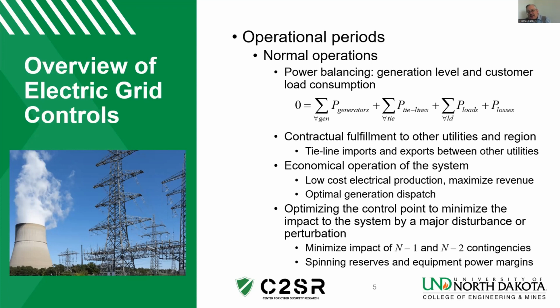But this also is biased because at the same time, in the energy management system, an optimal contingency analysis is taking place, to find the right operating point of the system. So contingency analysis, again, looks at making the system survivable after events taking place. So we look at the loss of one or two major pieces of equipment, and if that should occur, what should the operating point of the system be such that the system remains stable and in a place that the operators can continue to work short term till resources are restored or new resources are made available.